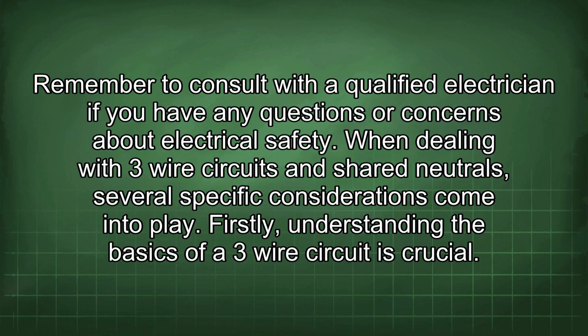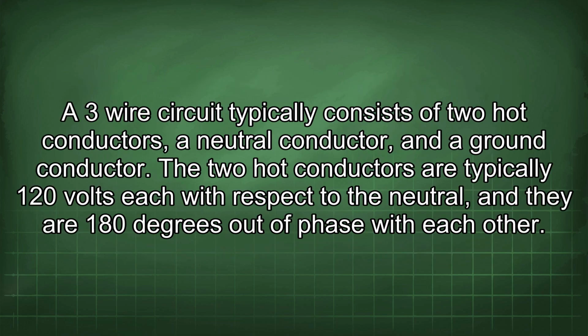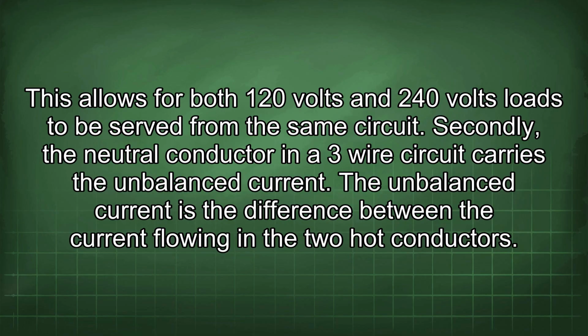When dealing with three-wire circuits and shared neutrals, several specific considerations come into play. Firstly, understanding the basics of a three-wire circuit is crucial. A three-wire circuit typically consists of two hot conductors, a neutral conductor, and a ground conductor. The two hot conductors are typically 120 volts each with respect to the neutral, and they are 180 degrees out of phase with each other. This allows for both 120 volts and 240 volts loads to be served from the same circuit.